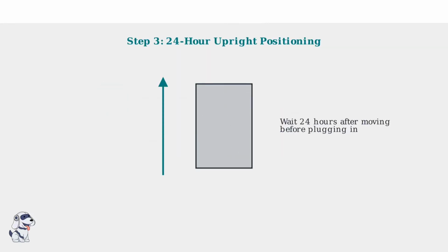If the unit was recently moved or transported, it must stand upright for at least 24 hours before plugging it in. This allows the refrigerant to settle properly and prevents compressor damage.